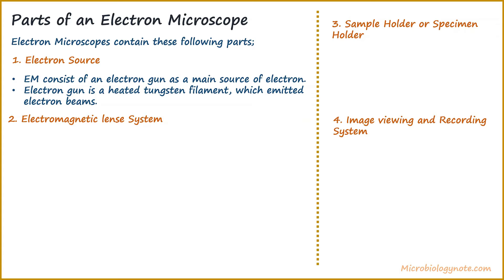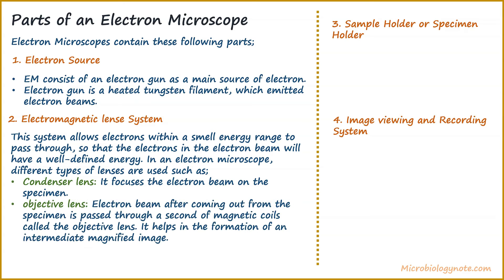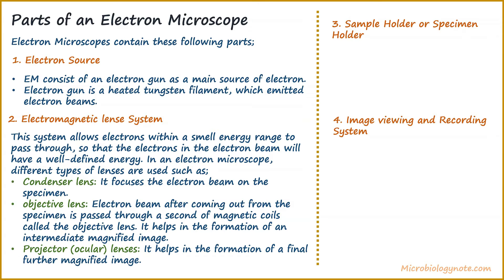The next part of an electron microscope is the electromagnetic lens system. This system allows electrons within a small energy range to pass through, so that the electrons in the beam will have a well-defined energy. Different types of lenses are used: the condenser lens focuses the electron beam on the specimen; the objective lens — through which the electron beam passes after coming out from the specimen — helps in the formation of an intermediate magnified image; and the projector or ocular lens helps in the formation of a final, further magnified image.